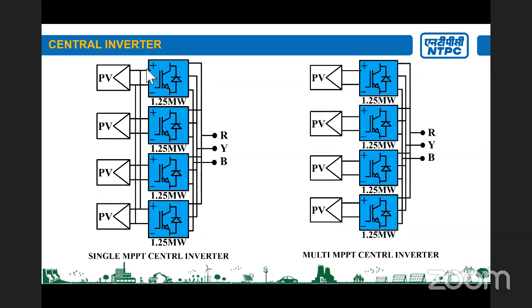Then, this was the configuration most of the manufacturers were offering. Now they themselves have shifted to multi MPPT central inverter topology. The issue in a single MPPT configuration is that since the multiple modules are connected with both DC and AC side parallel, there will always be some circulating current, or rather a disproportionate sharing of current because of parallel impedance. So current sharing will be different, and for that additional margin is also required.